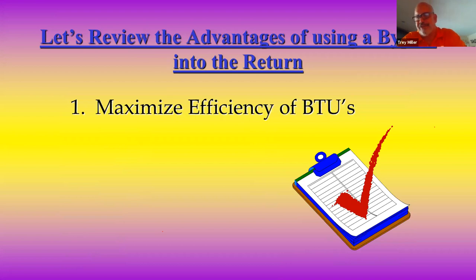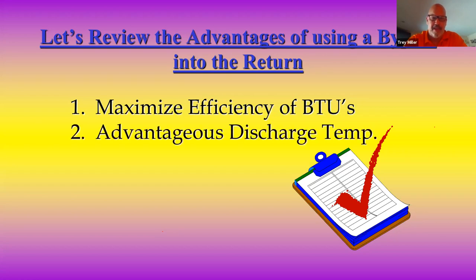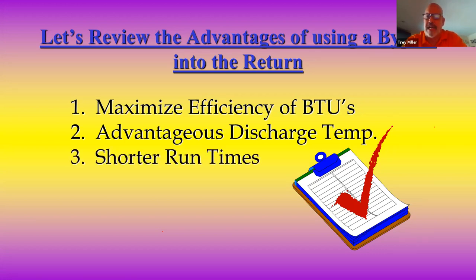And I'm not a guy who's going to tell you to bury dampers in ductwork, because you have to be able to access it for service in case we have a problem or scenario. Even though our dampers don't go bad very often, you still may need to service them every now and then. Advantageous discharge temperatures. Gentlemen, I'm going to be cooler in cooling, warmer in heating, which does nothing but result in shorter run times for your customer. Does nothing but save them money.